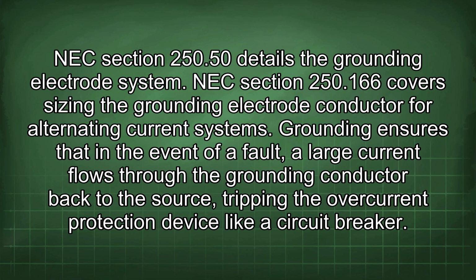NEC Section 250.166 covers sizing the grounding electrode conductor for alternating current systems. Grounding ensures that in the event of a fault, a large current flows through the grounding conductor back to the source, tripping the overcurrent protection device like a circuit breaker.